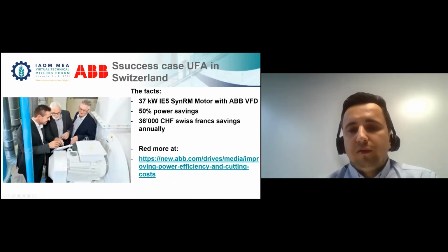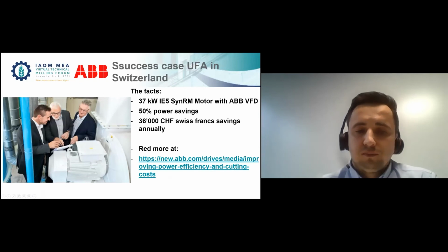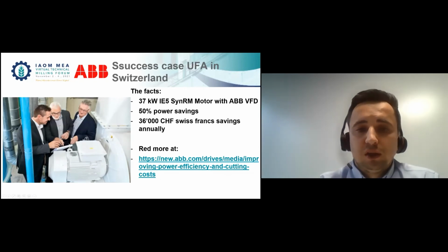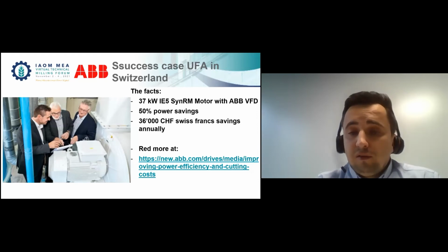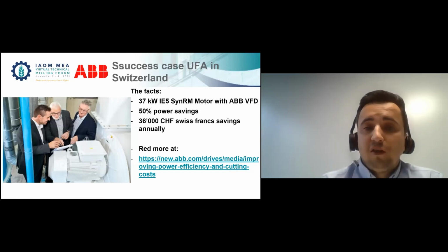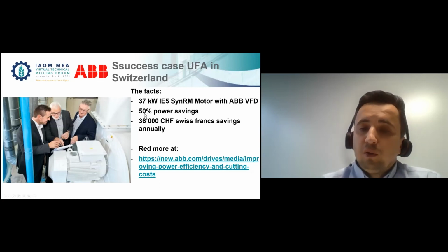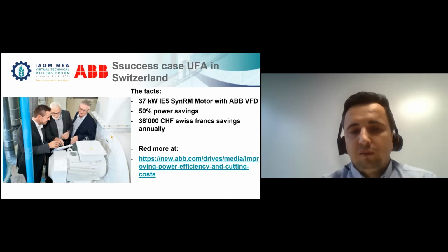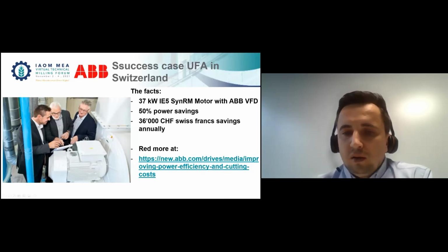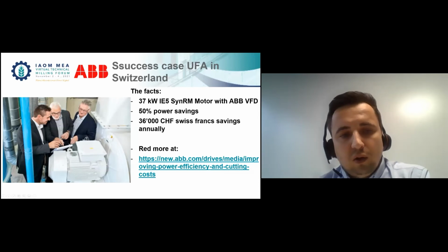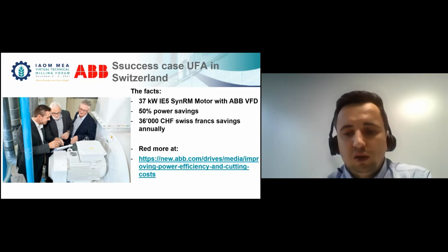We have here fact sheets where we have used it. It was for a milling application with Bühler together here in Switzerland with a synchronous IE5, a synchronous reluctance motor with a 37 kilowatt motor. They could save 50% of the energy costs for this type of blower. I'm sure that everybody has such blowers in the grain milling industry. The success story is here. It's not a new one. This technology exists quite a long time, but it's very important that everybody is aware that there are huge potentials for energy savings around.